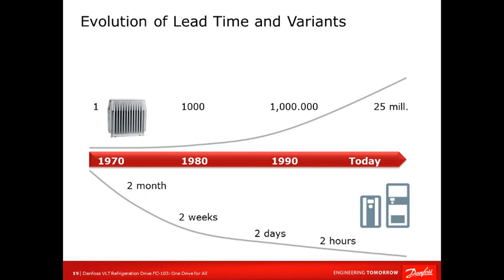And when I mentioned the Carlsberg application, in the middle top there on the left side, that was a VFD, a 5-horsepower, picture about 3 feet high, 3 feet wide, oil cooled. When you're looking at what's happened over time and the technology, it's quite amazing. You know, the lead times, for example, shown there in the bottom, now we can produce VFDs in less than 2 hours, where it used to be 2 months.